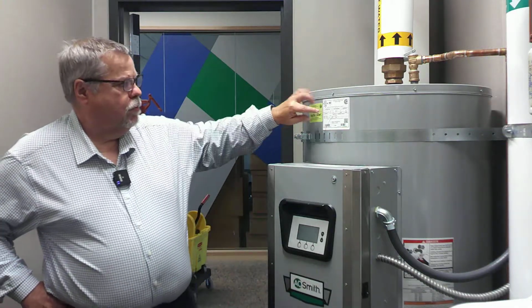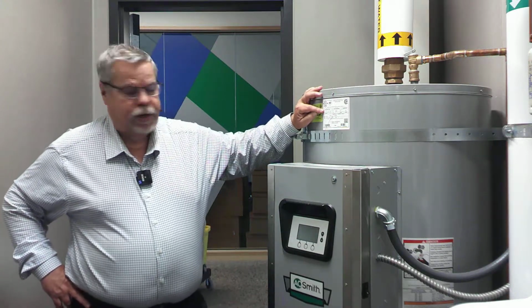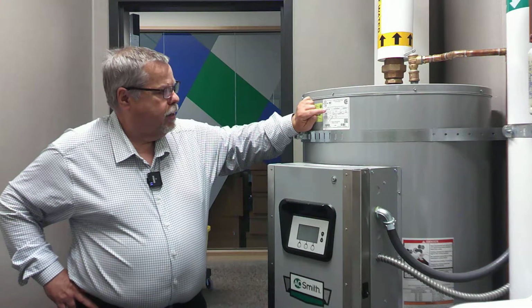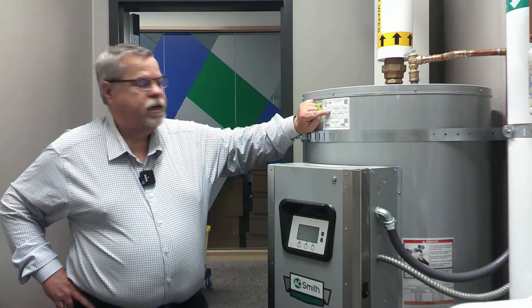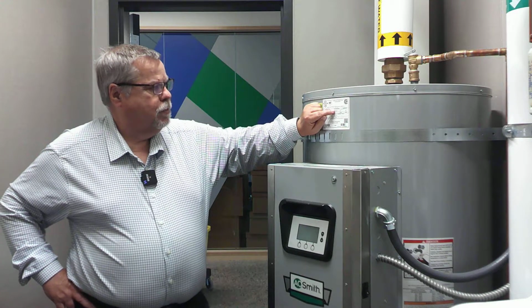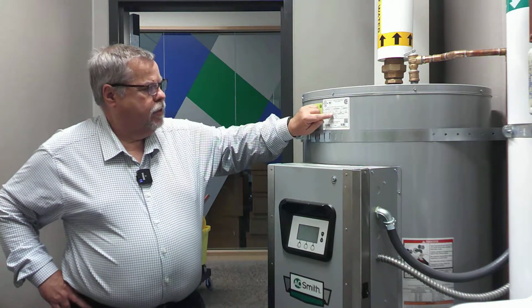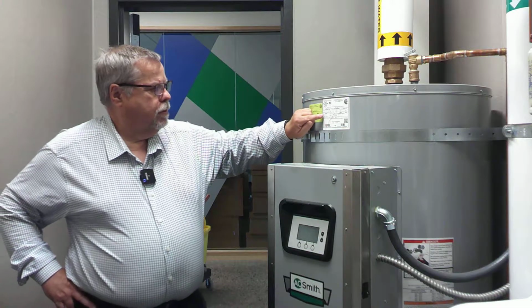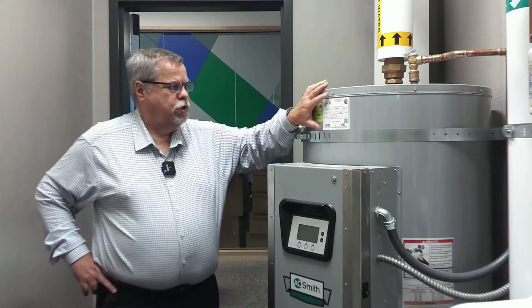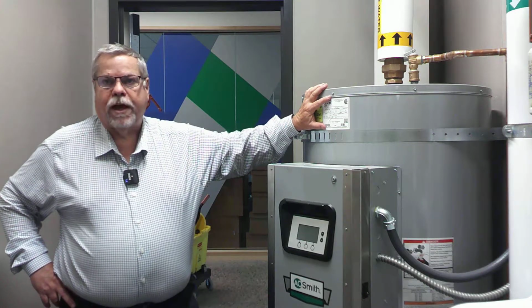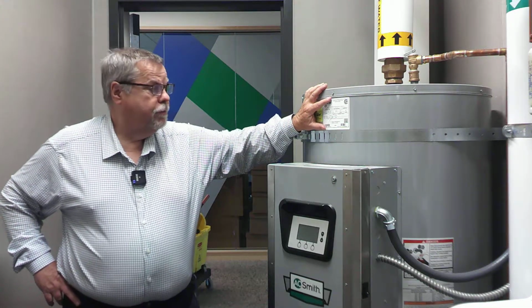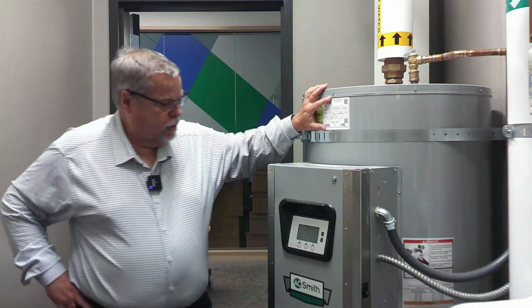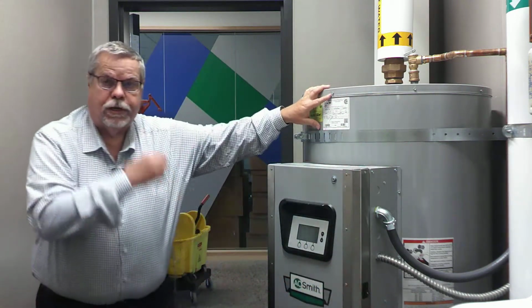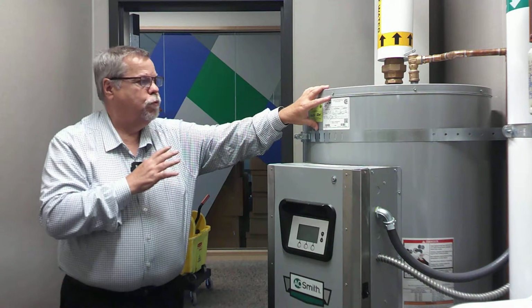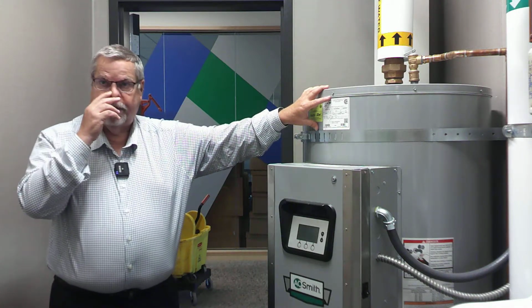Smith model. One of the important things you need to note is the serial number. The serial number here and model, the model is a DSE 65A200. The serial number is right here. It's 480 volt, one element, three phase. This is the information you would need in order to call the factory or Apollo Plumbing Apollo Mechanical for service. You have Apollo's number, but you also have an 800 number here for technical service.